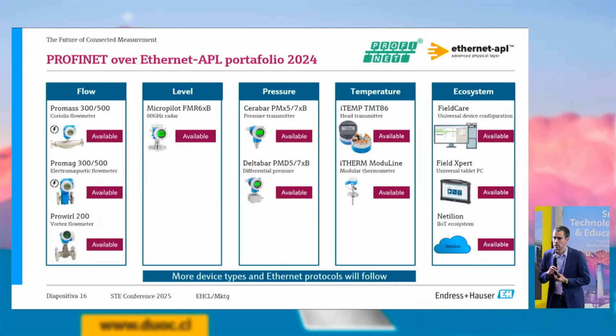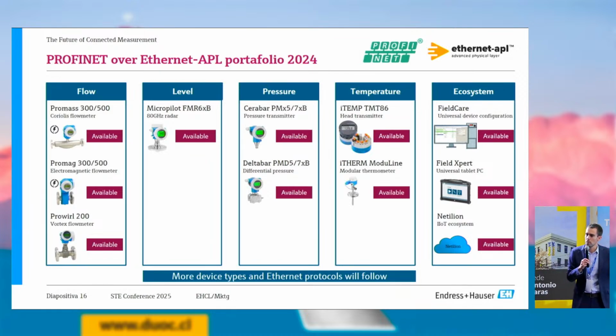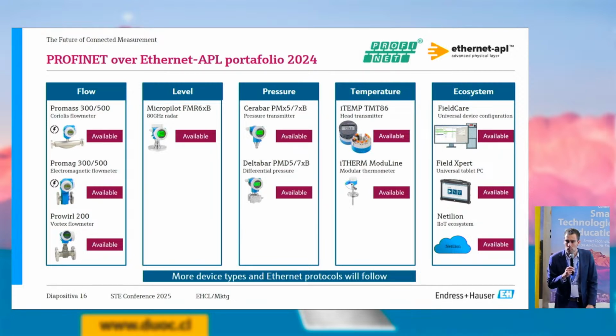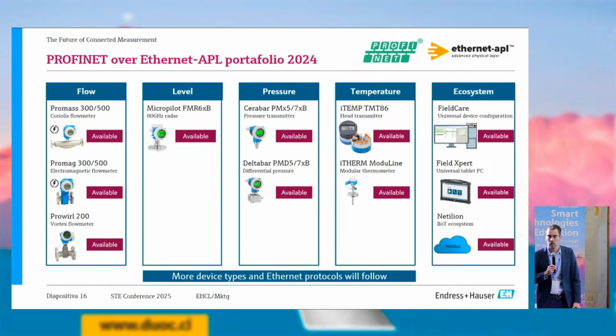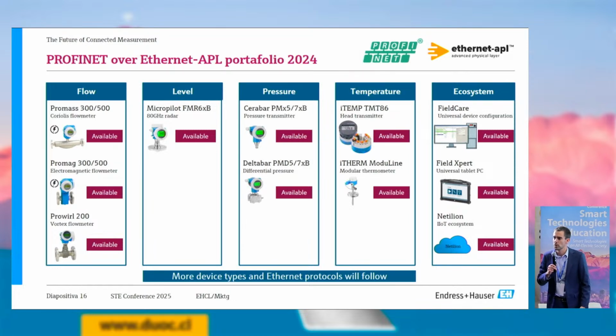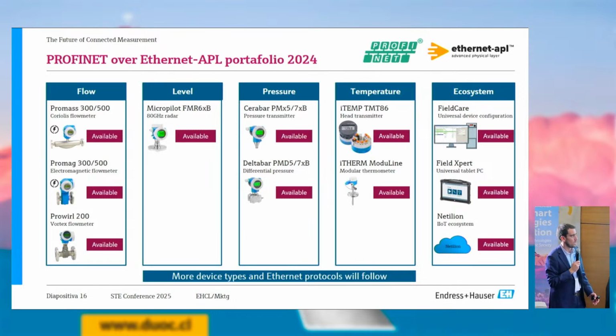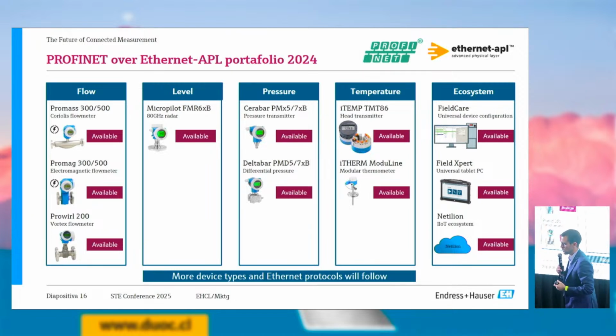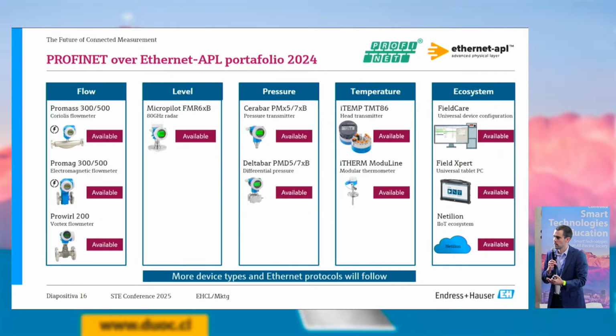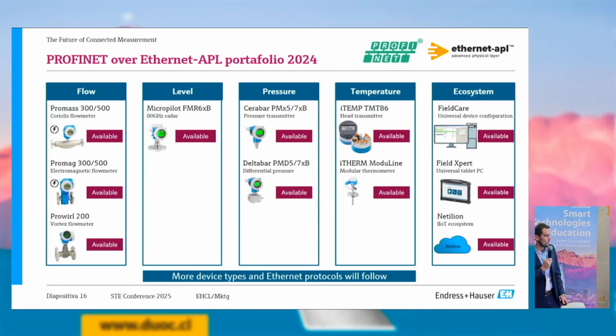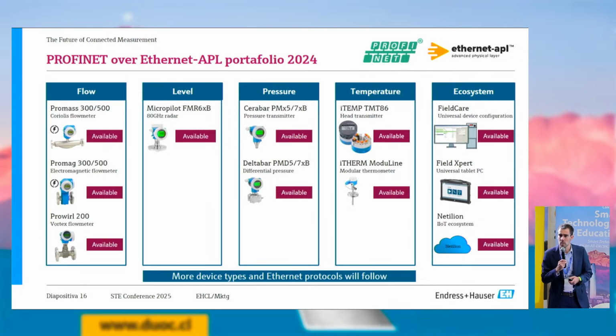Now I am really glad to show you a familiar picture of devices covering the areas of flow: Coriolis flow meters, mag meters, vortex meters for example to measure steam or air, radars to measure level, pressure in general, temperature, thermometers, and the ecosystem, meaning the asset management system, or this tablet that is a handheld able to verify and configure field devices. And Ethernet, that is something I will talk about in a couple more slides. There is more to come. The next system will be a liquid analysis transmitter to measure pH, for example, or other parameters.